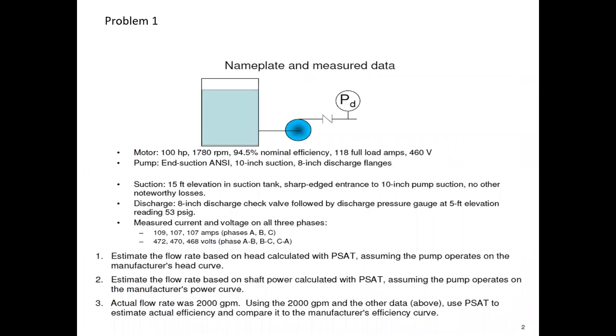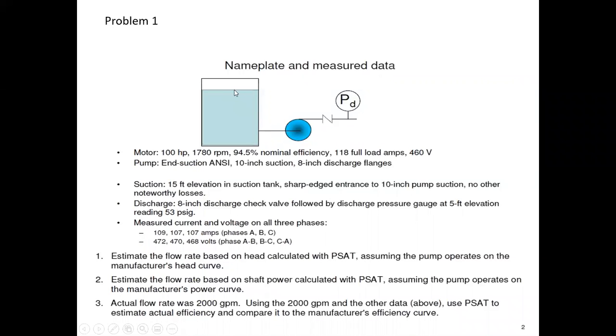Okay, so problem number one, we have some nameplate and measured data, and we have a diagram of the system that it goes to. So we have a suction tank with some elevation of fluid in it. There we go. And I will be given information about this. Then we have what'll be a sharp-edged inlet, and looks like no other fittings directly into the suction of the pump. On the discharge, we have a check valve, and then we have a pressure gauge downstream of the check valve.